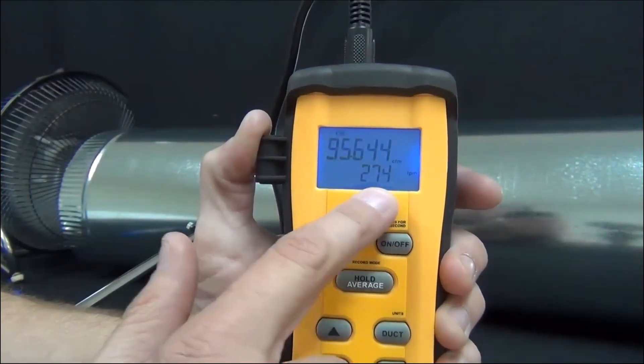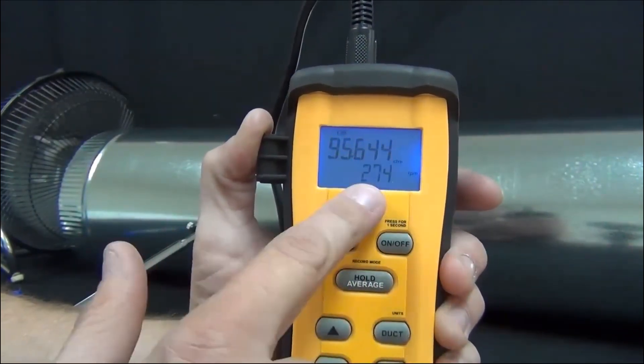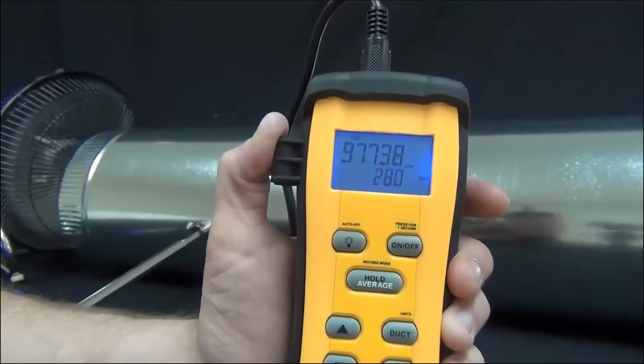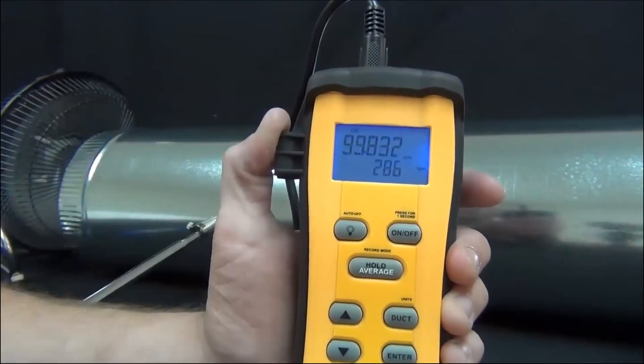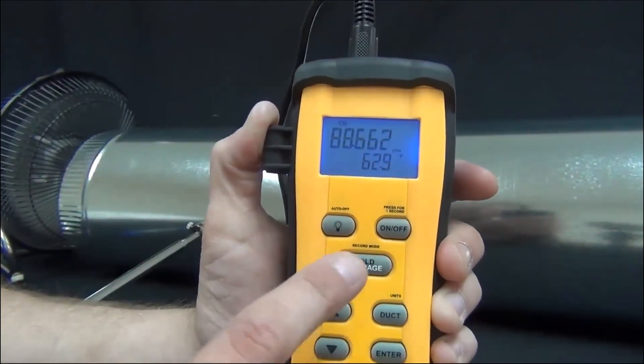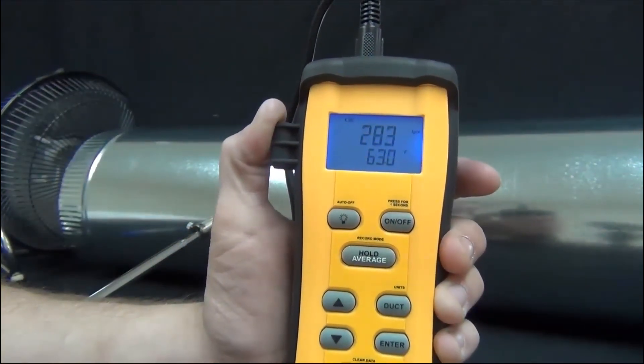And now you'll see that it's reading 274 feet per minute in the bottom display. So it's just taking the feet per minute, multiplying it by the area of an eight inch diameter duct, and calculating the CFM. Next mode is I can get CFM and temperature, and then back to feet per minute and Fahrenheit.